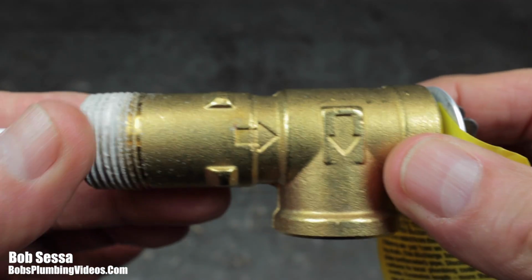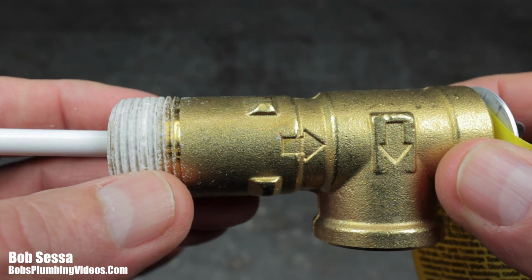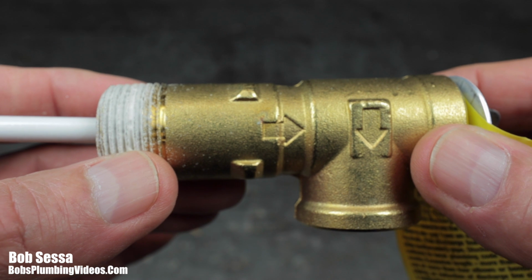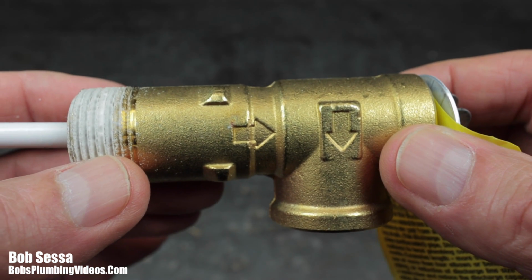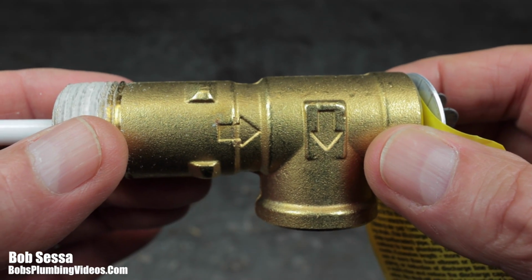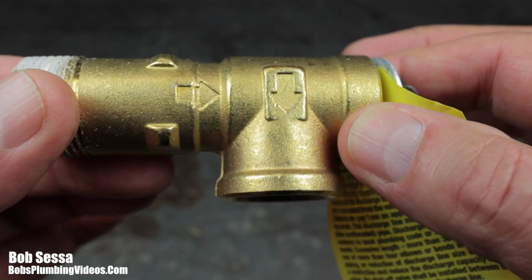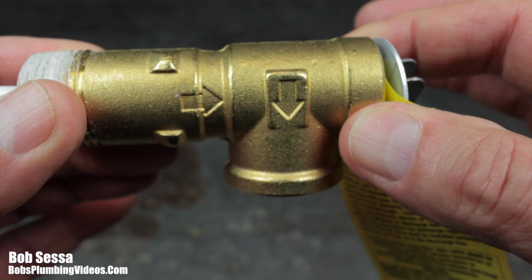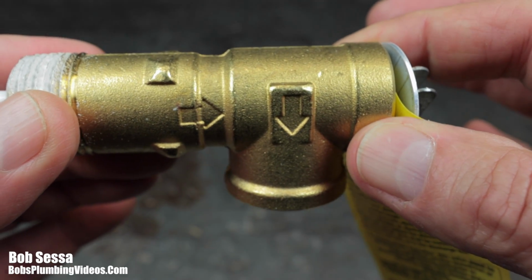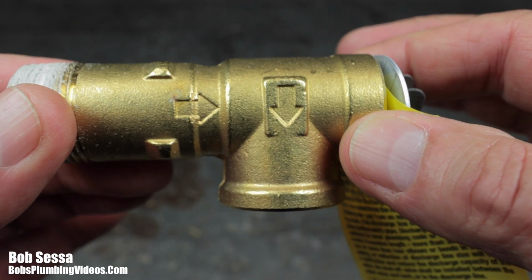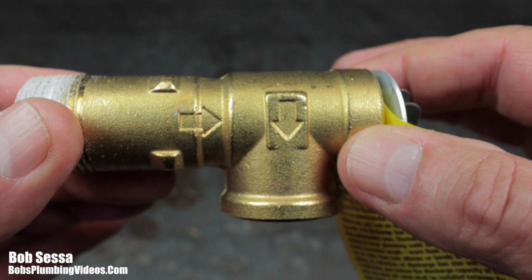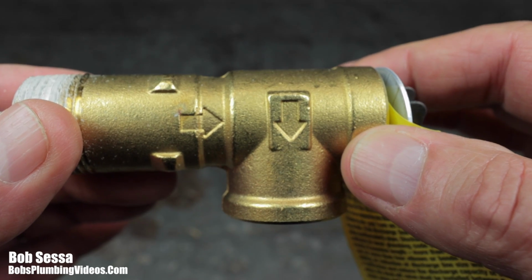All right, here we go. Typical T&P valve. To the left, you'll see the threads. This is generally where it's threaded into the water heater. You'll see the arrows on there denoting the direction of the flow. It goes toward the right, and then it goes out the outlet. And these are usually piped down via a drip tube anywhere between 12 and 18 inches above the floor. Plain end, no threads. Nobody wants any caps or plugs on it.